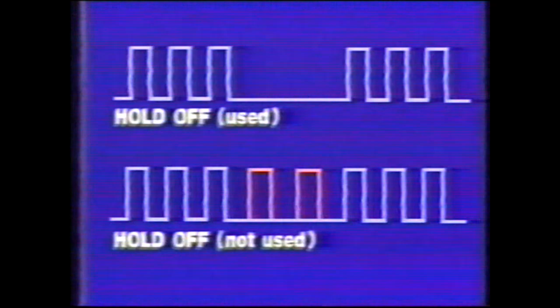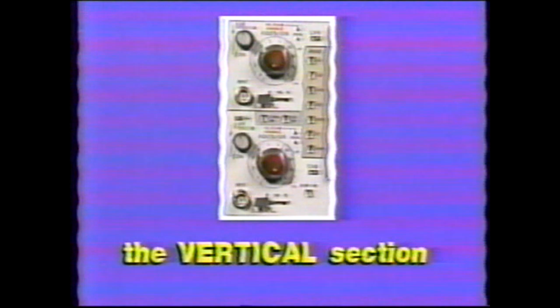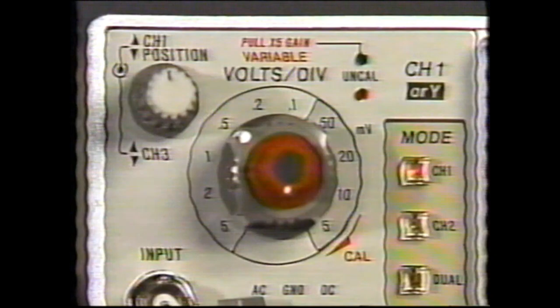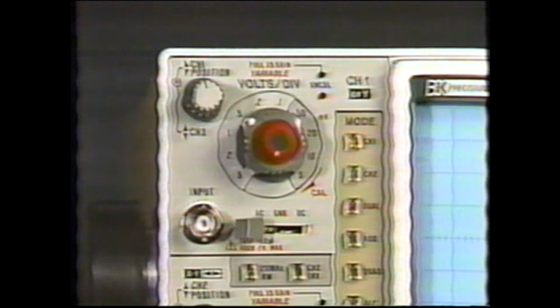The hold-off control allows the operator to choose, by altering the dead time between the end of one horizontal sweep and the beginning of the next, which trigger to synchronize in a complex trigger signal. Now let's look at the vertical section, which controls the Y-axis, amplitude, or the up-down axis of the scope. The vertical section includes coupling, position controls, the vertical attenuator, uncalibrated lights, vernier controls, and ×5 gain.